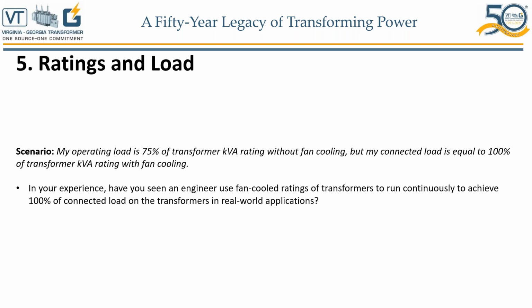So that gauge, when it gets to, say, 85 degrees, or 65, depending on how we set it up, is going to start your cooling devices. It's going to start your fans, your pumps, and other things. The same thing applies to the top oil temperature. So what I am getting to is that the answer really depends on the gauges and how they are programmed to turn the cooling devices on or off. And that goes with the loading of the transformer itself.